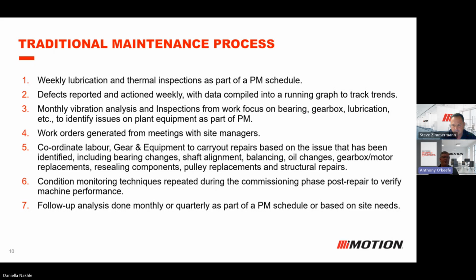We also take thermal imaging and record operating temperatures of equipment, so we have a very basic condition monitoring of the assets we're servicing. This gives us the opportunity to record changes in operating conditions, whether visually something doesn't look right, or something doesn't sound right, or the temperature has increased in a particular piece of equipment. So then we start running graphs and trending, having a baseline to work against.